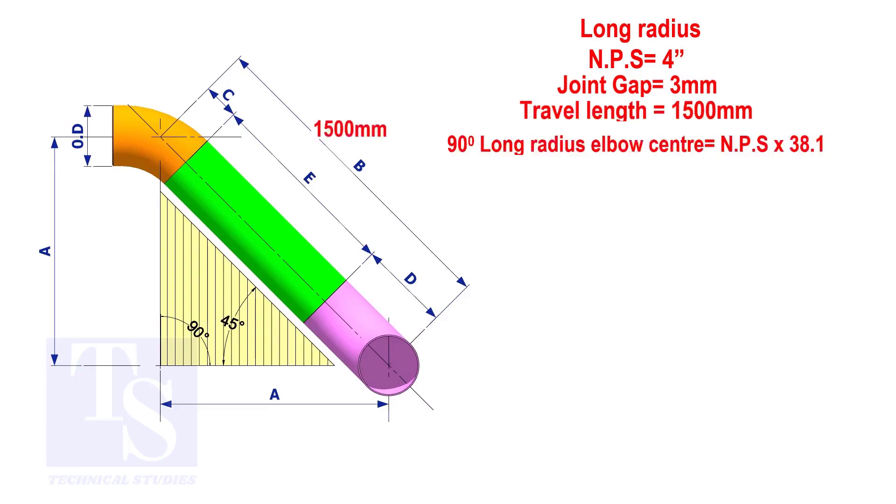The elbow center is the nominal pipe size multiplied by 38.1. So, the elbow center of the 90 degree elbow is 152.4 millimeters.